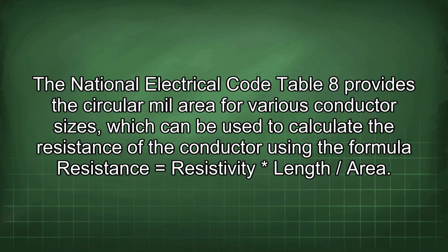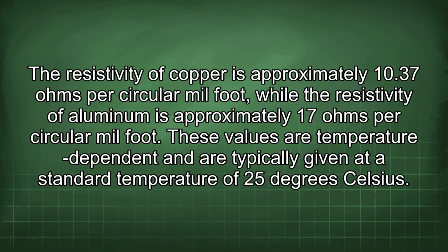The National Electrical Code Table 8 provides the circular mil area for various conductor sizes, which can be used to calculate the resistance of the conductor using the formula resistance equals resistivity * length/area. The resistivity of copper is approximately 10.37 ohms per circular mil-foot, while the resistivity of aluminum is approximately 17 ohms per circular mil-foot. These values are temperature dependent and are typically given at a standard temperature of 25 degrees Celsius.